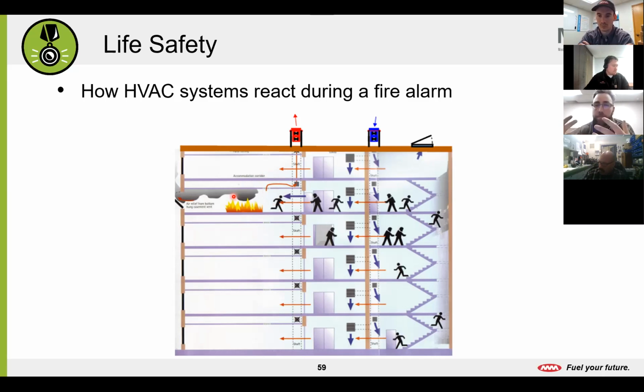We're trying to keep that smoke from moving outside of the space, right? If we're in a negative, we're pulling air from other spaces in, versus being in a positive where we're trying to expel the air contained within the space out. So we're trying to contain that. On the flip side, we have our stairwell pressurization fan. What that's doing is putting your entire stairwell into a positive pressure. And its sole job is to create a positive barrier. Again, with the corridor being in a negative, and the stairwell being positive, we're trying to expel air out. So if any of that smoke makes it out of that space, it's not going to migrate into our stairwell because it's going to hit that positive barrier, which is pushing back. So it's going to keep our stairwell smoke free and allow us the best chance to get down to the bottom floor and exit the building here.